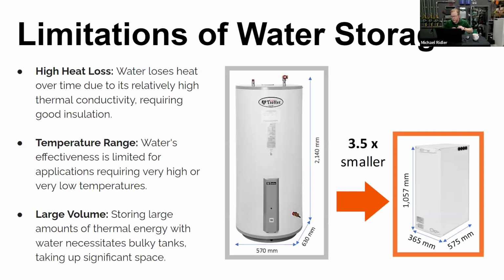That's the equivalent of 300 gallons of water, which is not insignificant. So what you're talking about is I can actually store 4 tons of capacity, which is the capacity of that battery, and fit it in a very small footprint. I can stick that in a closet, under a staircase. It's typically 3.5 to 4 times smaller than what you'd typically see in storage.